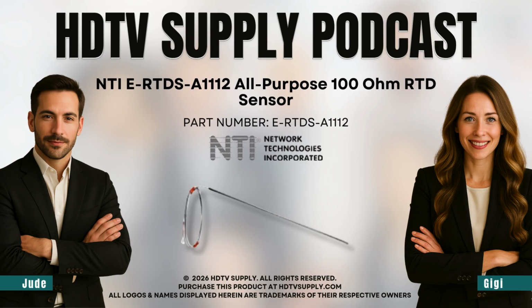Okay, so here's where I think we find the real nugget. This difference between its total range and its accuracy range. Exactly. The manufacturer says it can be used across that massive window we talked about. But they only guarantee the really high accuracy, we're talking plus or minus 0.27 degrees Fahrenheit, in a much smaller zone. A much smaller zone, from minus 148 up to 842 degrees Fahrenheit. So that's its sweet spot. That's where it's rock solid reliable. Outside of that, it still works, but maintaining that perfect linear accuracy gets, well, much harder. So it's a universal tool, but for surgical precision, you have to stay within that core range.